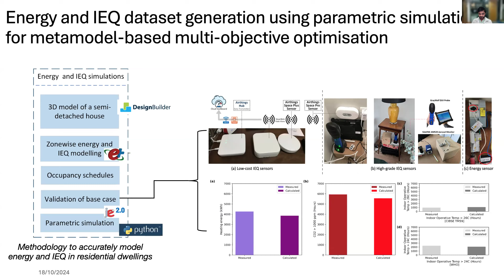Once all of these were incorporated into the models, I ran the simulations, and for the base case I used the sensor data I had collected and validated my base case against it. As you can see, the difference in heating consumption, CO2 concentration greater than 1000 ppm in hours, and indoor air temperature shows approximately 5 to 7% variation between the measured values and the calculated values.